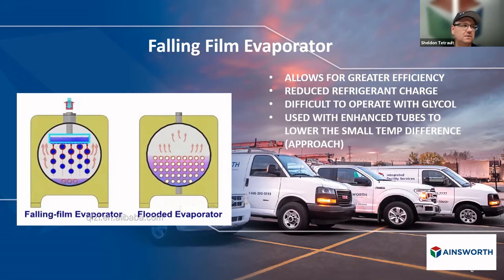Can we talk a little bit about different efficiencies from older chillers to newer chillers, like in kilowatts per ton? That I find a bit challenging, because of what you see in the field and what you see in the engineering literature, there are so many variables. But the kilowatts per ton are getting down to like 0.3, it's crazy. But that's something I don't focus on a lot, because just like sizing a cooling loop or condenser water loop based on the pump curve, it gets you close, but nothing substitutes for physically measuring it in the system. So that's where the field experience, I think, really kicks in.